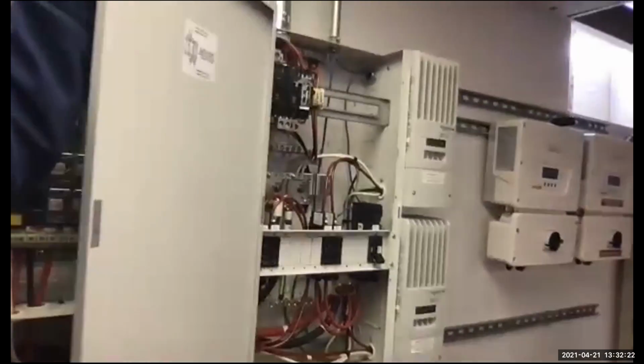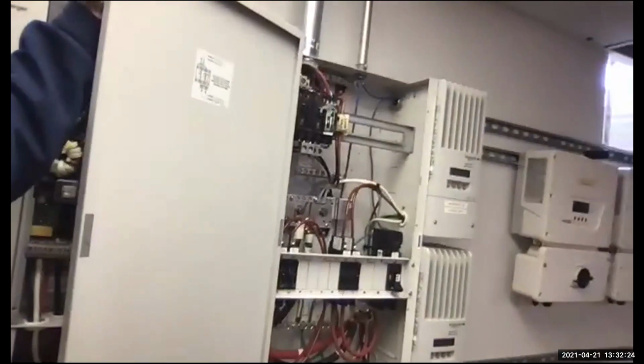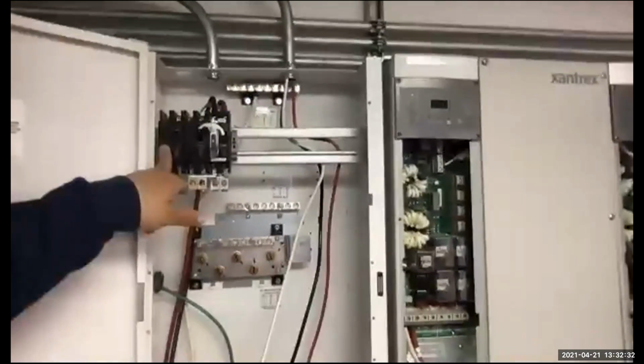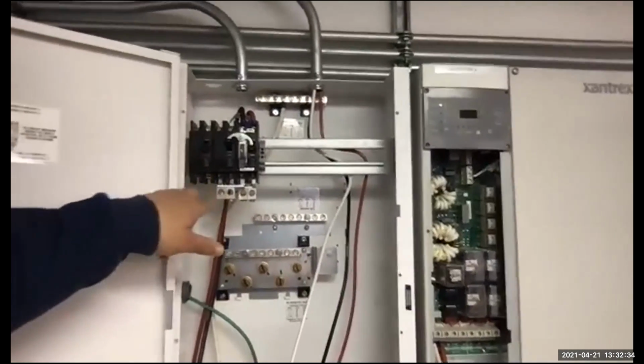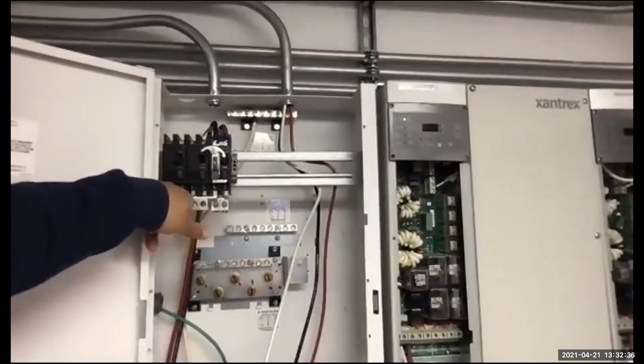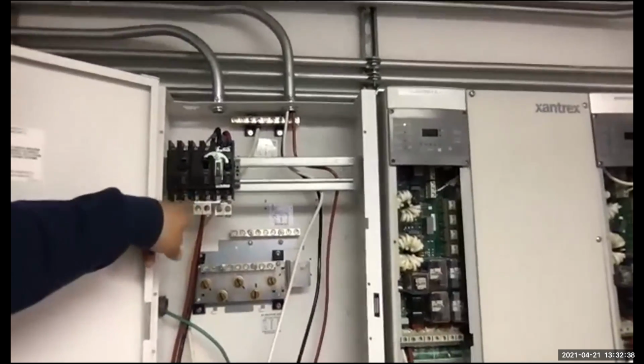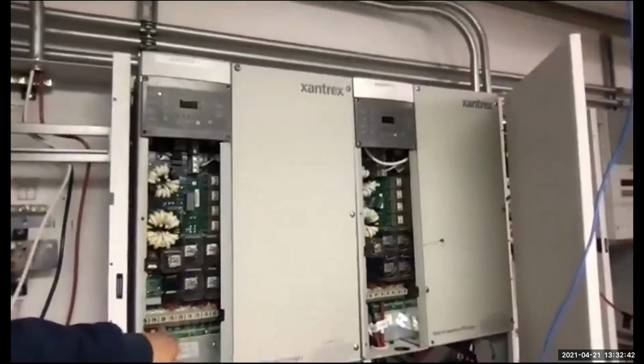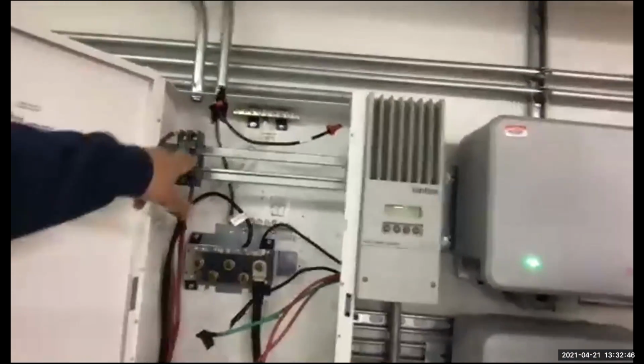Now we can do that part without hooking the thing up to the grid. So you literally have these 2 breakers here, you got this and this. We're going to take 2 wires from the bottom side of this breaker, and we're going to bring them down and up into this grid AC. Same thing over here, you've got 1 breaker.